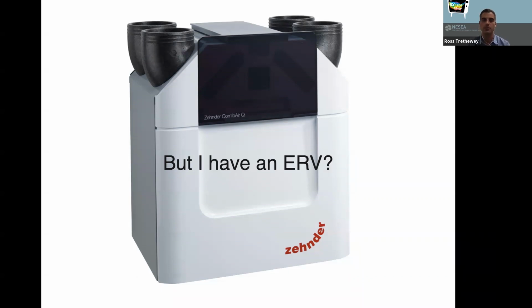It's neutral pressure. If I run a 600 CFM kitchen exhaust fan, the ERV is not going to do anything realistically to help me with that negative pressure in that building. So you need makeup air to offset the kitchen range exhaust, especially with 600 CFM in this example. ERV is not going to solve you there. ERVs are great, huge fan. It's great for ventilation, whole house. It's great for indoor air quality. I know you guys have talked at length about that, but that's that.